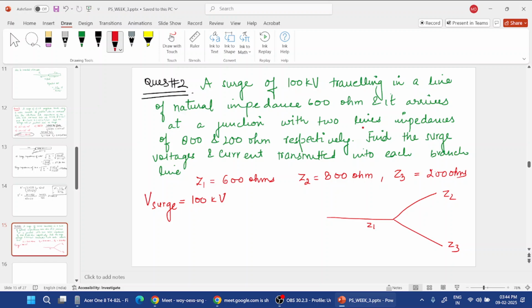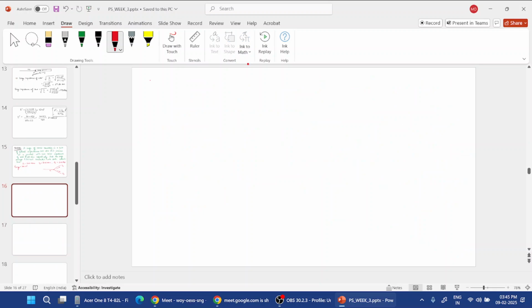So what happens here is that when the surge reaches a joint, it will suffer reflection, and the transmitted voltage will travel. So we should know the formula to calculate the transmitted voltage when a surge is divided into two lines, like a T joint. Let's say this is E: it is (2V/Z1) by (1/Z1 + 1/Z2 + 1/Z3).